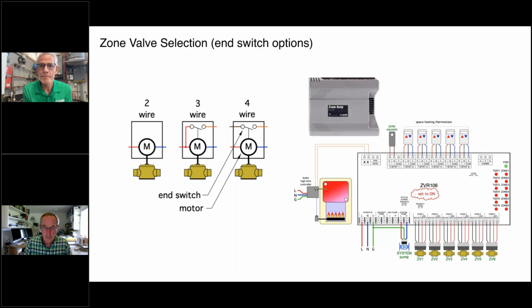And then Caleffi also makes the zone relay panels here for both zone valves as well as zone circulators. And it makes the wiring easy. Again, these will be in Hydronics 36, but basically the thermostats wire in across the top. The zone valves wire in across the bottom. You can wire the end switches in. System pump is on here. There are other circulator options depending on how the system is configured. But these are commonly used today to simplify the wiring when you're working with a multi-zone system.